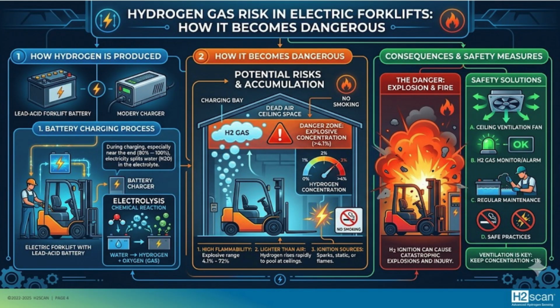However, if you have a fan failure or hydrogen accumulation exceeds the amount of airflow available to evacuate those gases, then it could go into the LEL, or lower explosive limit. And so this is just the 4% where hydrogen becomes explosive. And then the consequences are you could have explosion or fire. We have had reports where the explosion is so great it damages a ceiling or a wall, and could even injure personnel. And so our safety solution is to ventilate the room, monitor hydrogen gas, and then of course make sure that your batteries are well maintained.